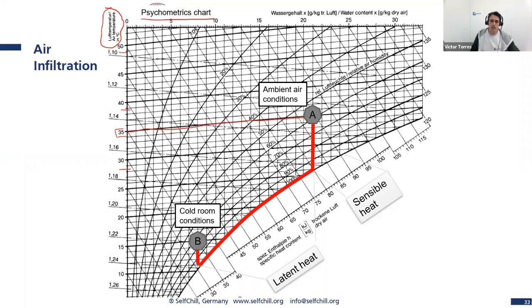Relative humidity starts from 100%, 90, 80%, 60%, 50, 40%, and so on. So if you know the temperature and relative humidity of the air, you already know where you are in the psychrometric diagram. If we consider 55% relative humidity, then we are here. That's all—very nice, you're already using the psychrometric chart.